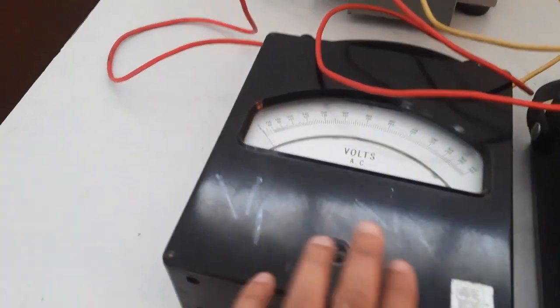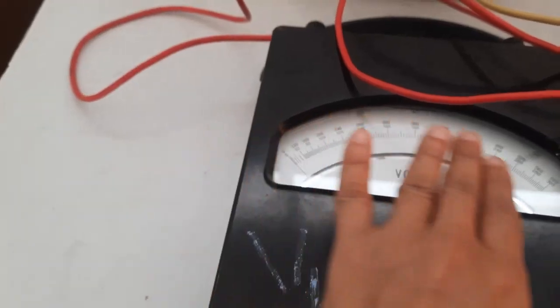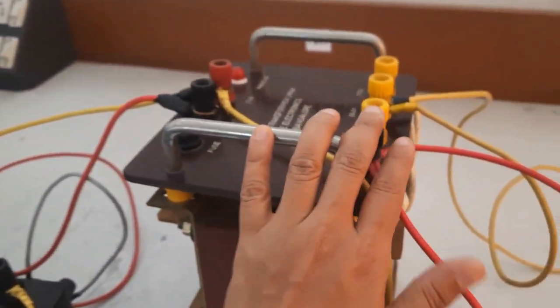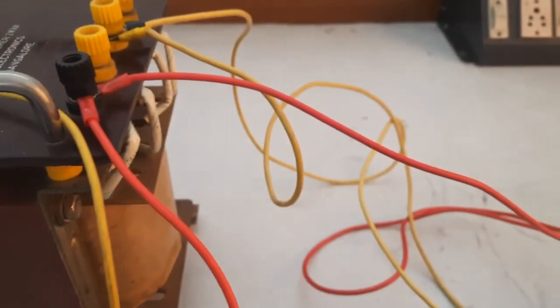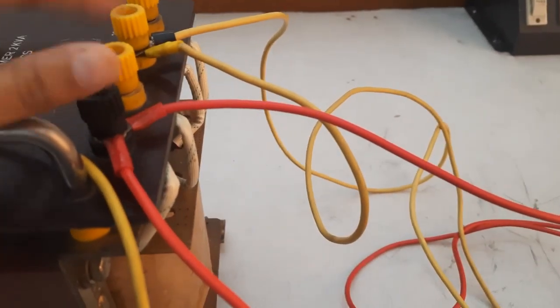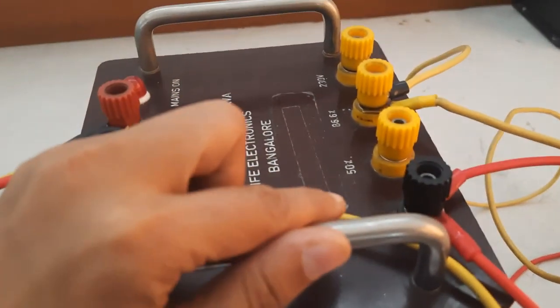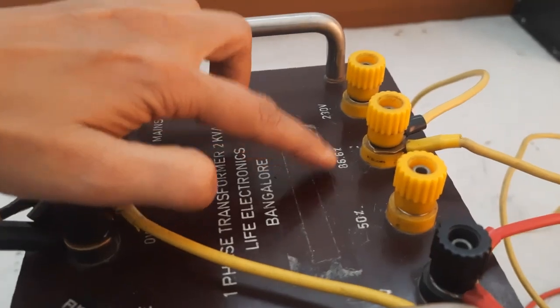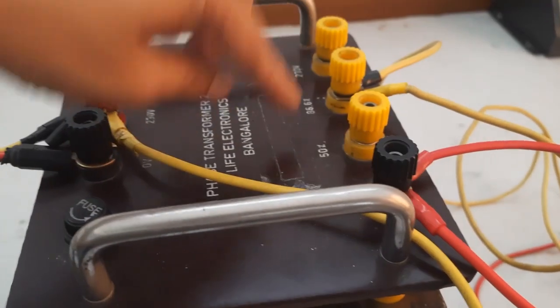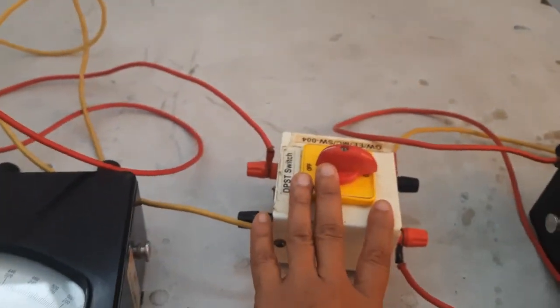Then we have to connect V1, that is 0 to 300 volts, across the auto transformer terminal. That is the primary side connection. Next, coming to the secondary side connection, we have to connect it for 0 to 200 volts. In order to get the 200 volts, we have to use the 86.6% tapping. So from 0 and the 86.6% tapping, we have to make a connection to the DPST switch.